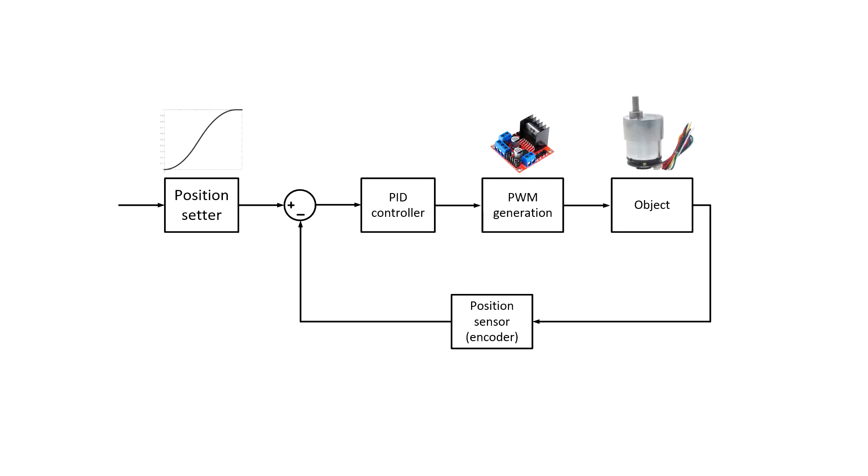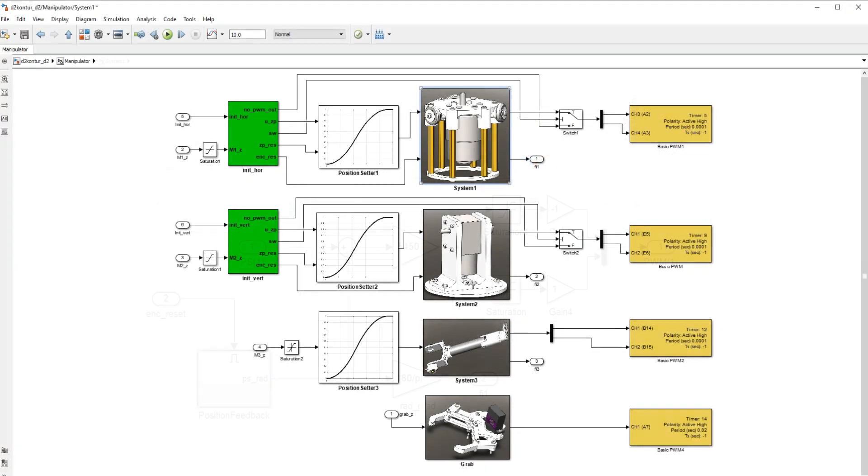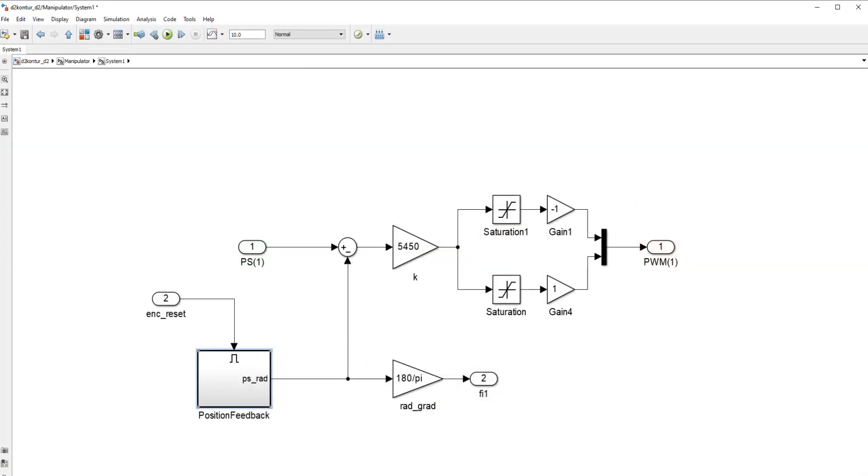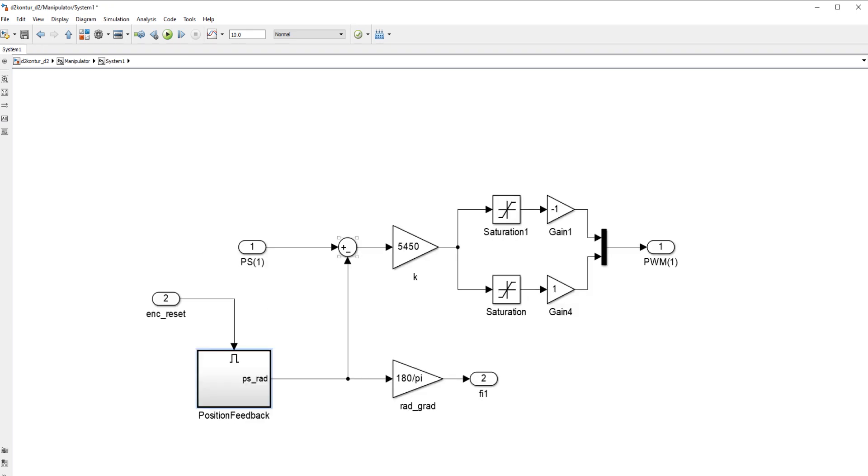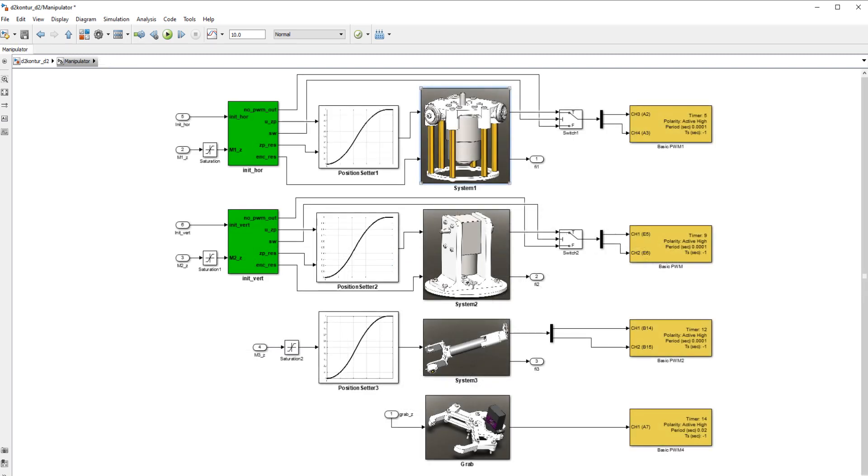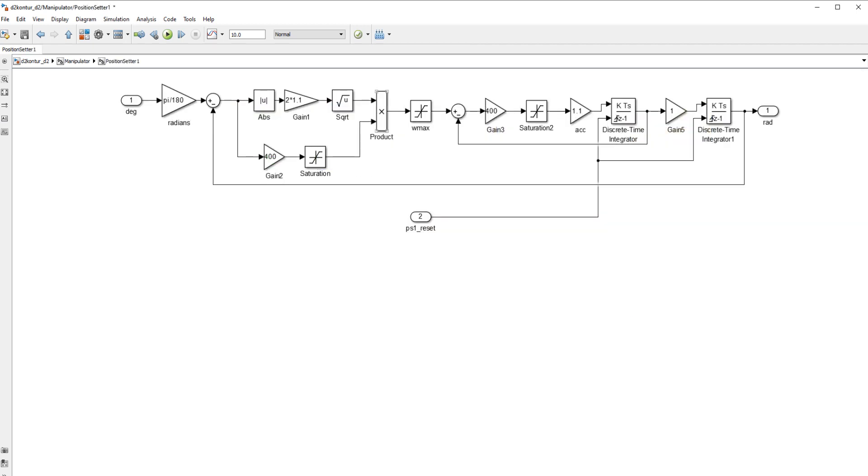A closed loop control system was created for each motor. The position feedback signal comes from the encoder read block. Then it's converted to a bipolar signal and converted to radians. The difference between the required angle and the current angle is multiplied by the proper coefficient. After which the signal is sent to the pulse-width modulation unit. The input signal passes through the position setter, which allows us to limit the maximum speed and acceleration of the motor.